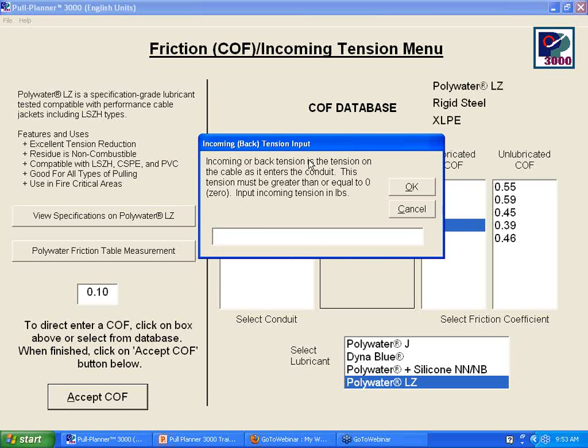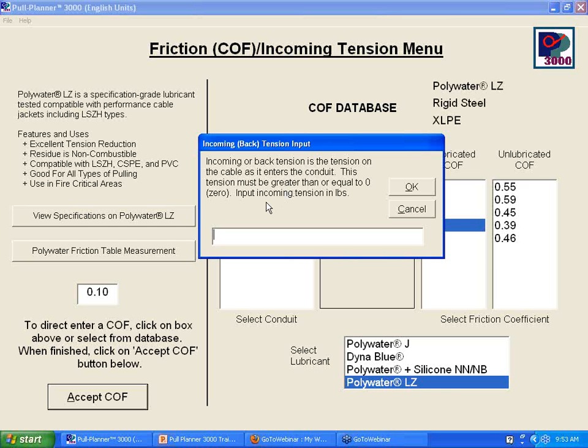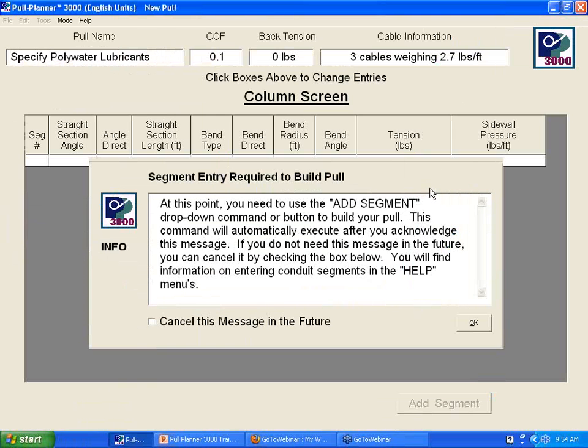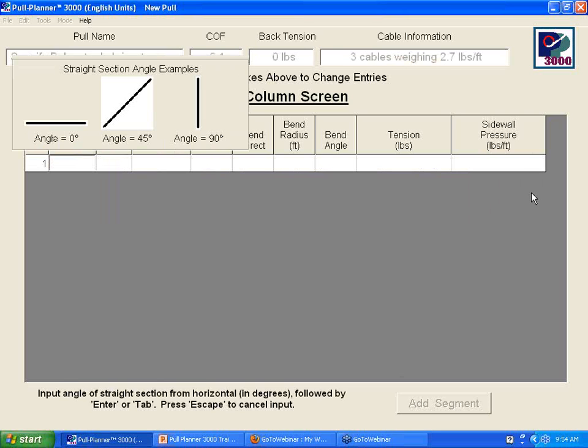The next prompt asks for incoming or back tension. Remember, a full reel of cable weighs much more than a half-full reel, creating back tension. Vertical pulling scenarios also contribute. We'll enter zero for now, but I'll show you how much back tension affects ending tension and sidewall pressure. Click OK to proceed to the conduit segment entry screen.